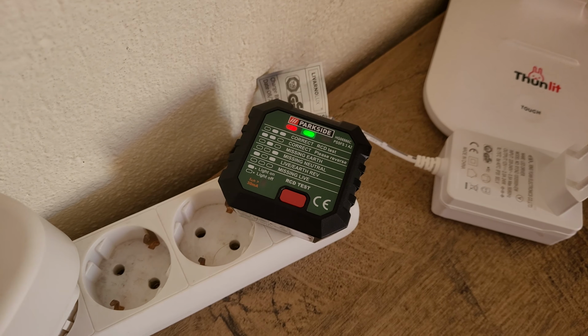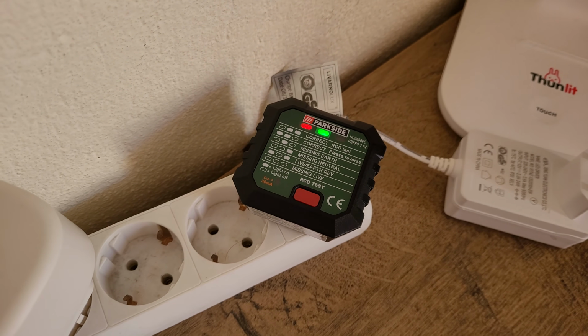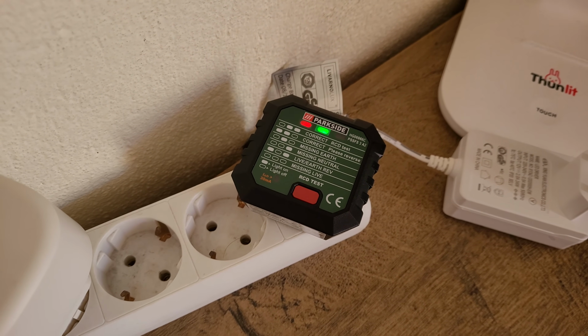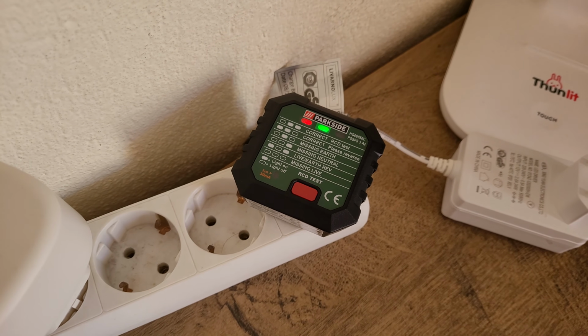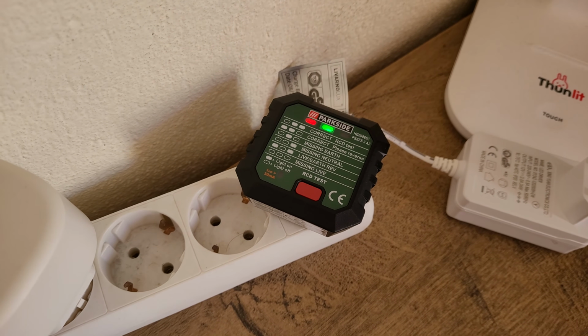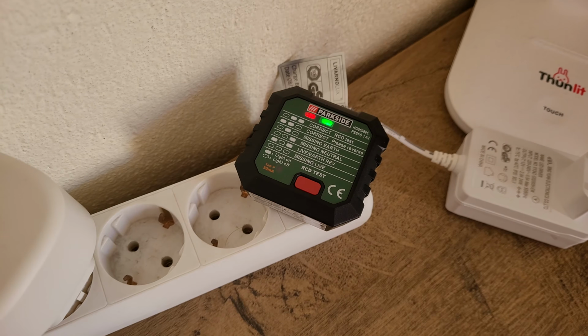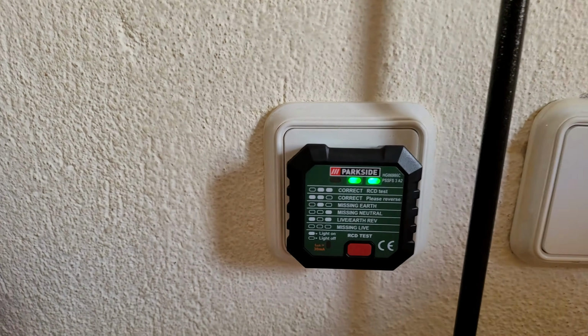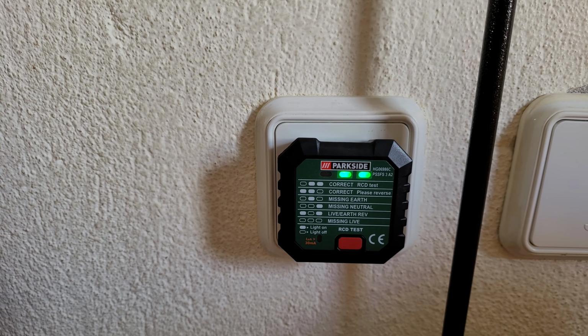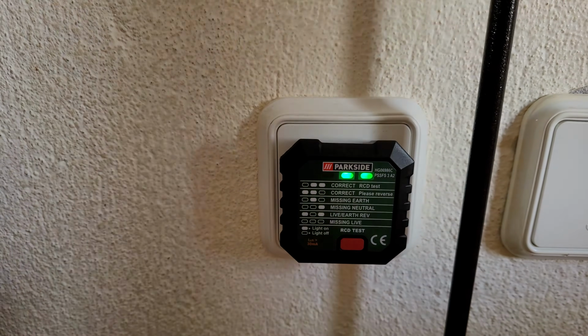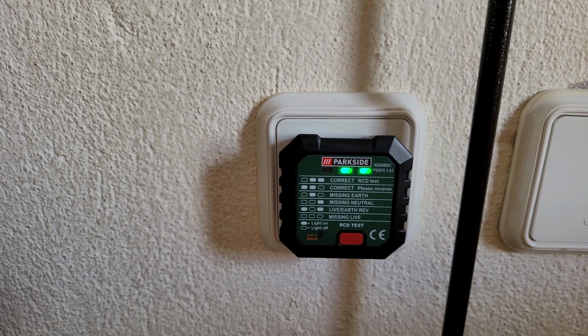On a multiple socket, we can see we've got a problem - one green light and one red. That means we've got a missing earth. Now I need to check the main socket, and that's how we will know if the problem is in this multiple socket or in the main socket. There is the main socket, but here everything is okay - we've got 2 green lights. That means the problem is in the multiple socket.